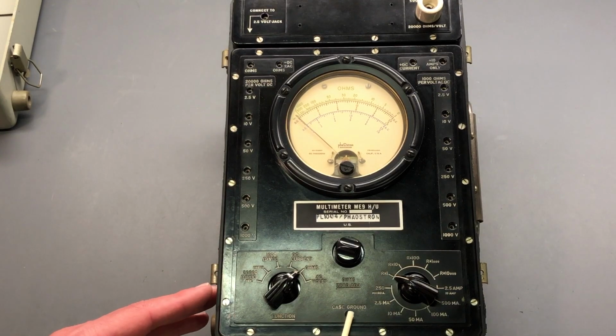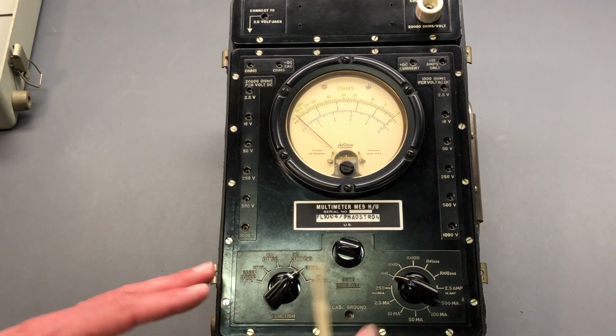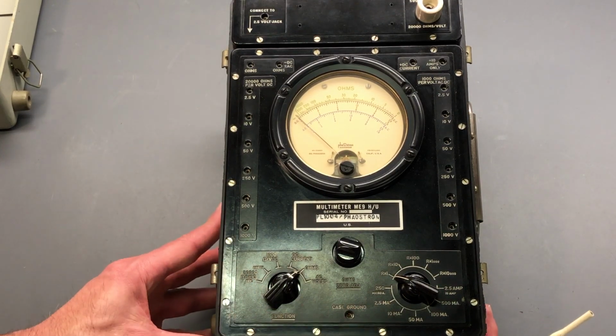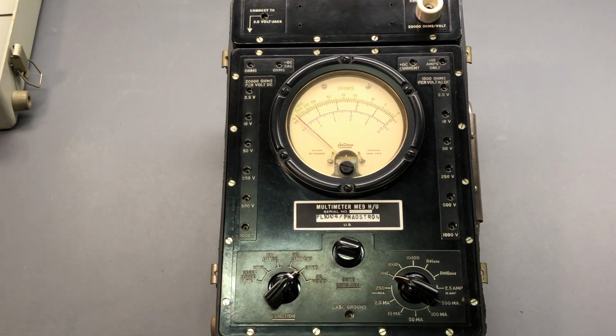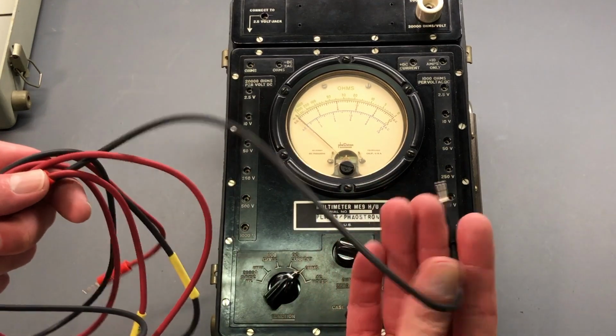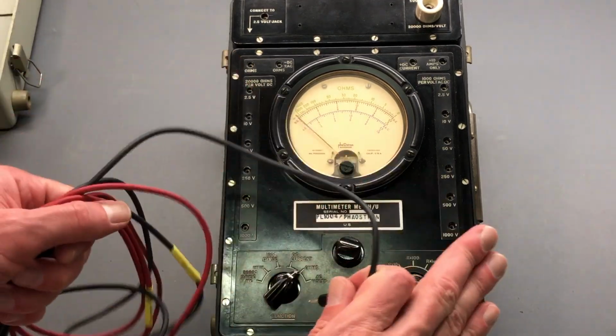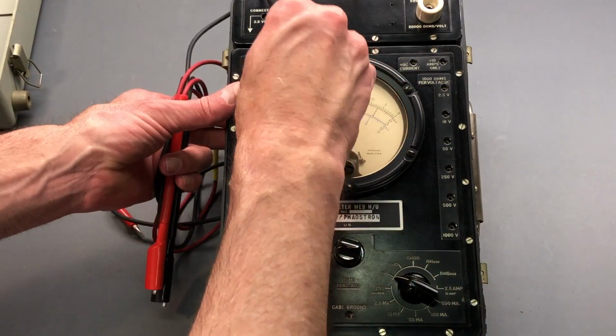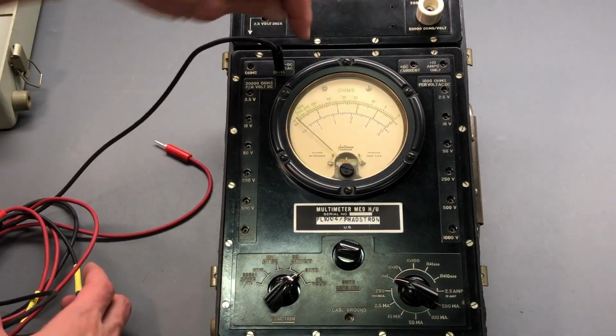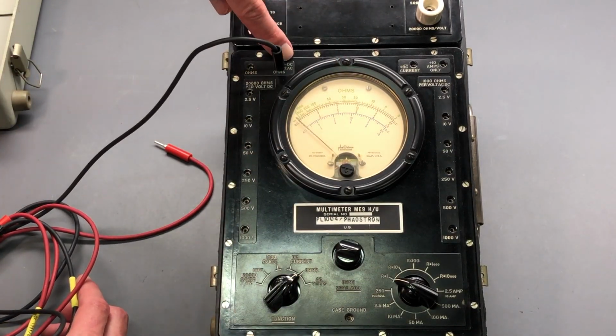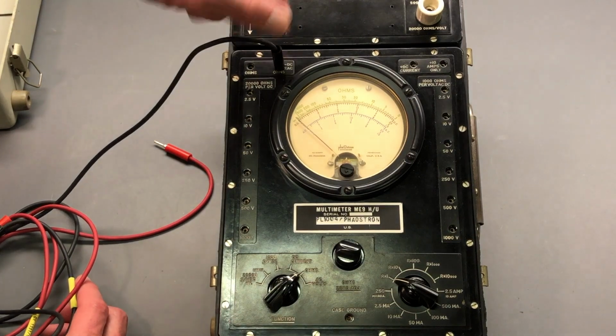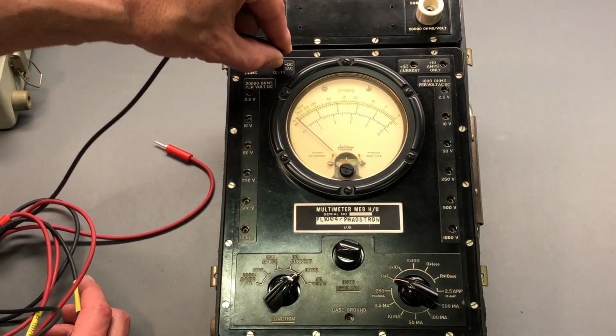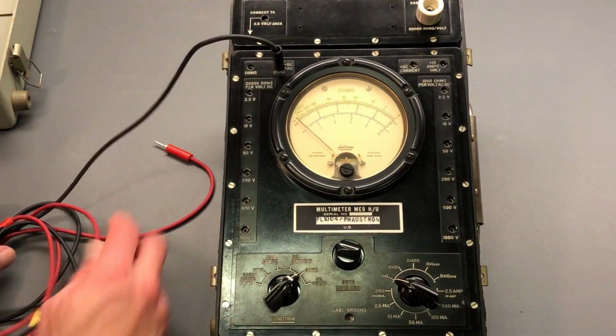This case ground is not the same as where the negative test lead goes. We'll get to that in a moment on where that actually plugs in. So if you have your test leads, the negative test lead, or the black test lead, for everything that this meter is capable of doing remains right here in the jack that says ohms, and then negative DC plus minus AC. So it always remains there. This never leaves this connection right here.